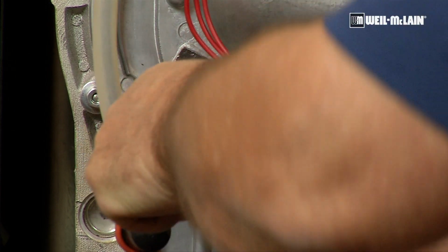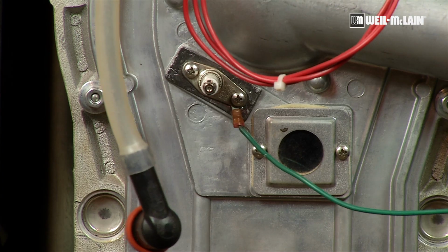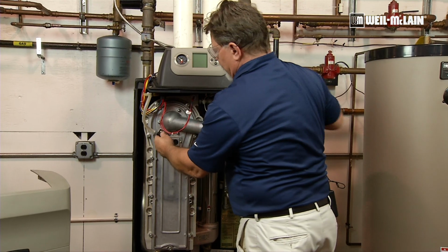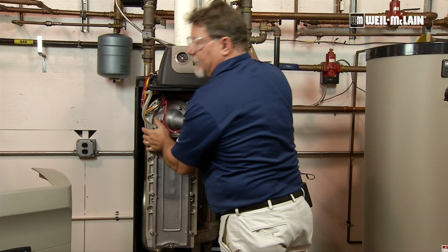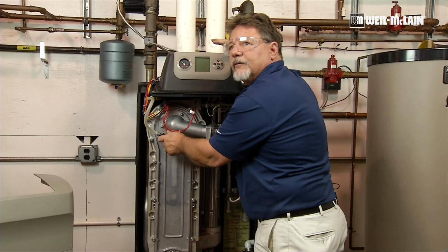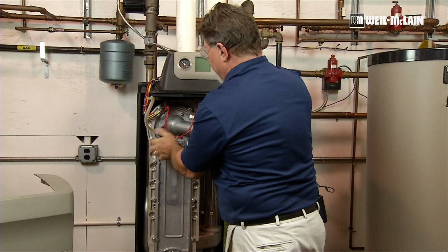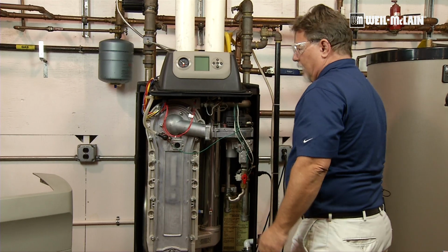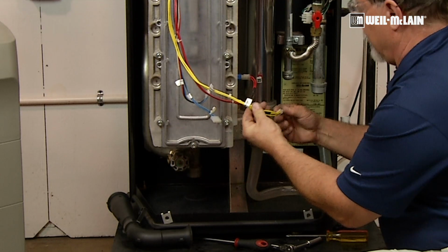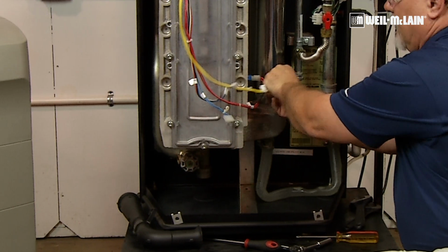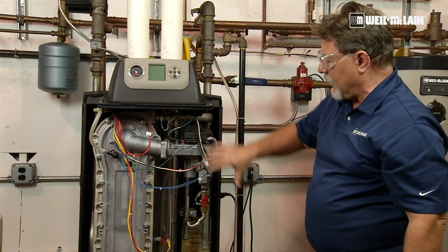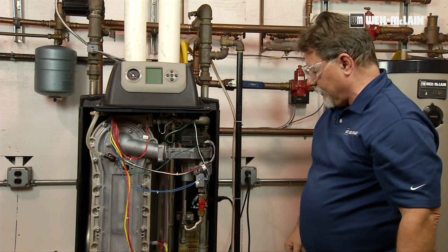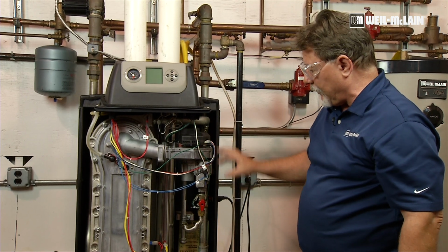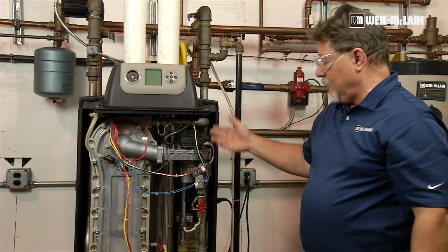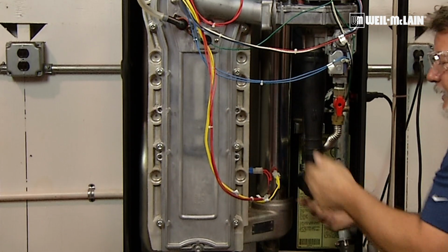So I'll start with the ground wire that attaches to the igniter. At that point, we can put the igniter cable on. Make sure you hear it click when you put it on the igniter. We need a good connection there. The next step would be to attach the rest of the boiler wiring. Okay, all the wires have been reconnected. We've put the boiler back together. There's only one other piece that we need to reinstall besides the door, and that would be the air silencer.